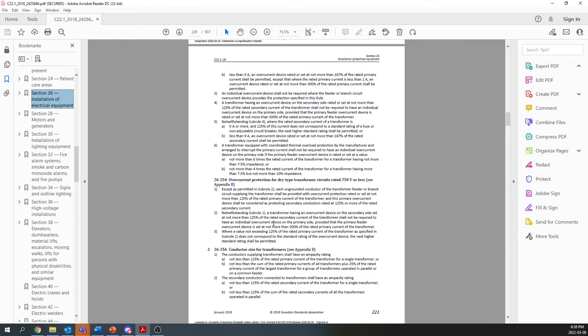It is confusing, but you need to know them for designing the ampacity of the primary circuit breaker that is feeding a transformer, or the secondary side circuit breaker that is feeding the downstream load. Sometimes you need both, sometimes you only need one.